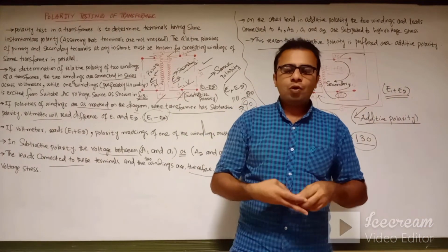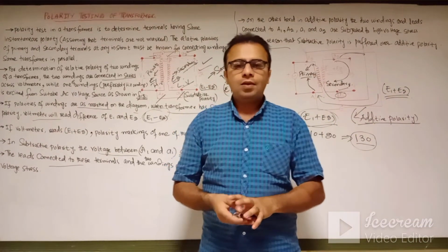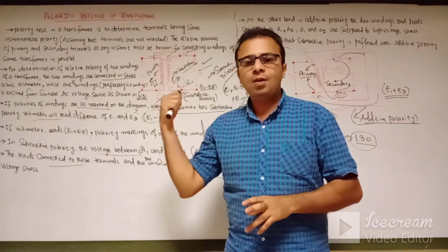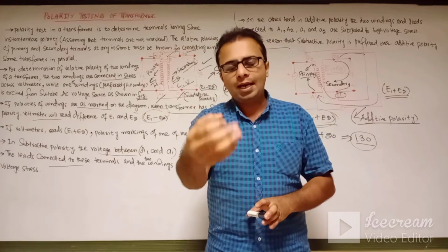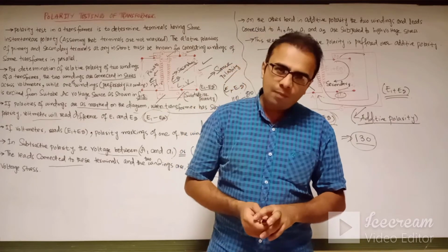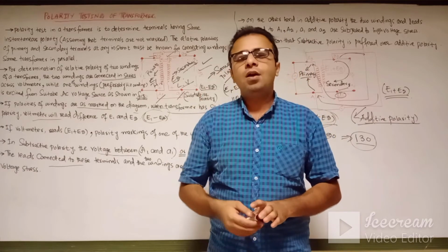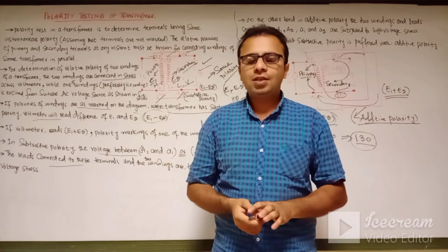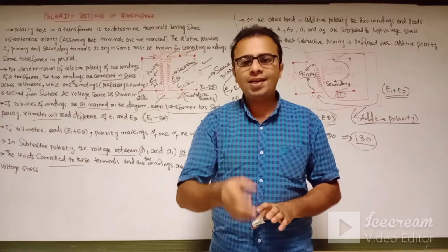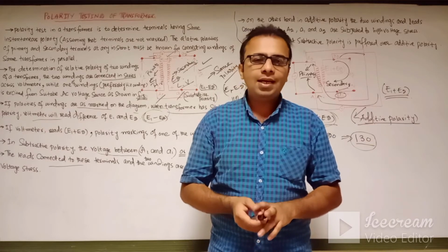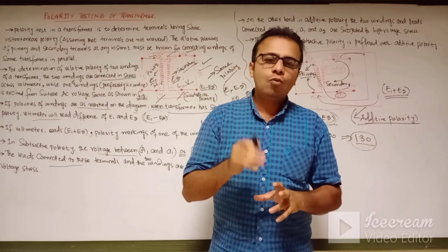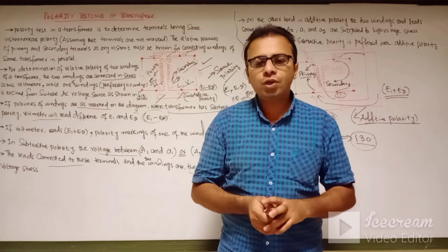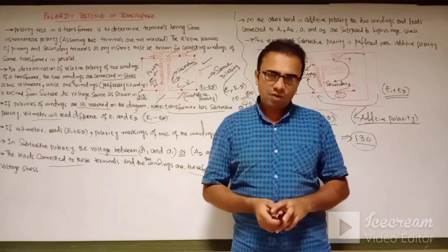Now I am going to summarize this lecture. Transformers are connected in parallel across the infinite bus bar, so we need polarity testing of the transformer to determine whether it has the same polarity or the opposite polarity. In the subtractive polarity test, where the two windings are connected with the same polarity, the voltmeter gives us the reading of the difference of the two induced EMFs, as shown in the figure, E1 minus E2.